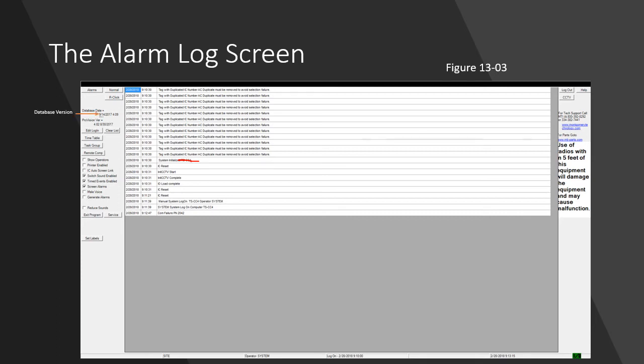First of all, you have the database version listed here, and this can be important if you're not seeing the things that you expect you should be seeing on the screen. Maybe you added a button but you're not seeing that. Then you might want to look to this date here to see effectively what version of the database you're operating on. So if you made a change today and you changed the database file for this particular touchscreen, but then you're not seeing that button that you added, and you go and look here and the date's off, then obviously you're not operating on that same database.